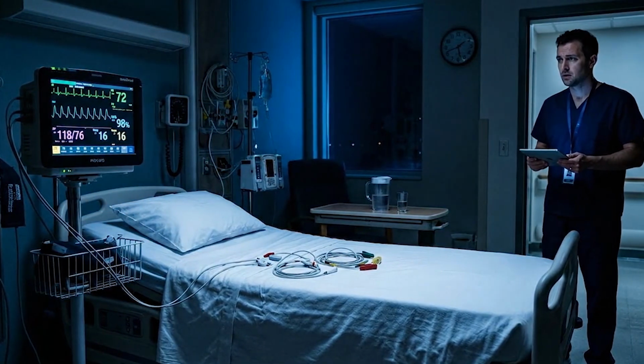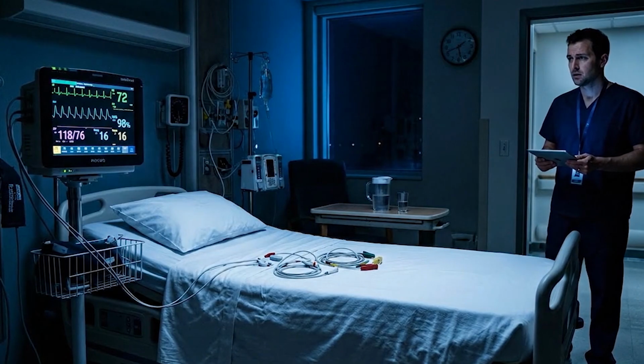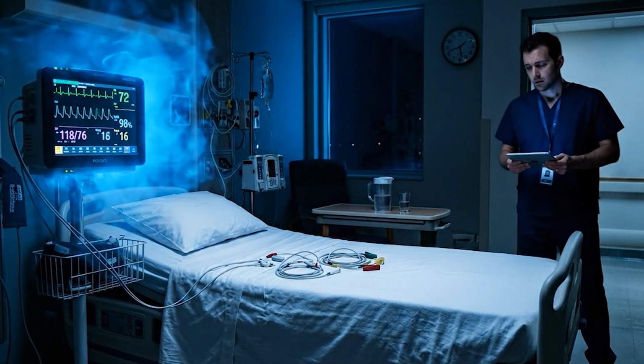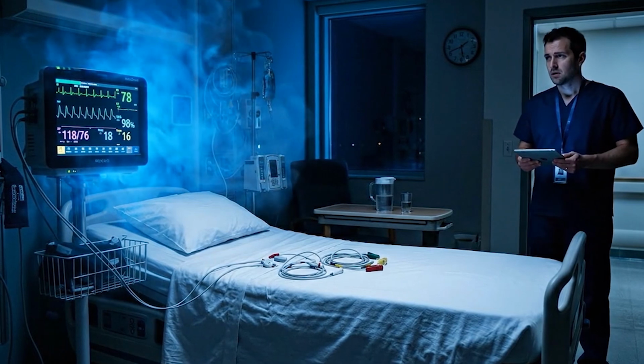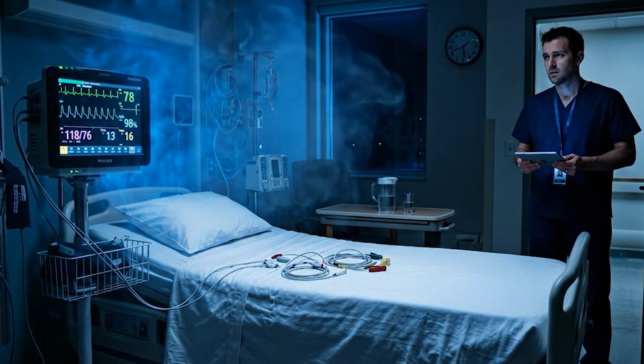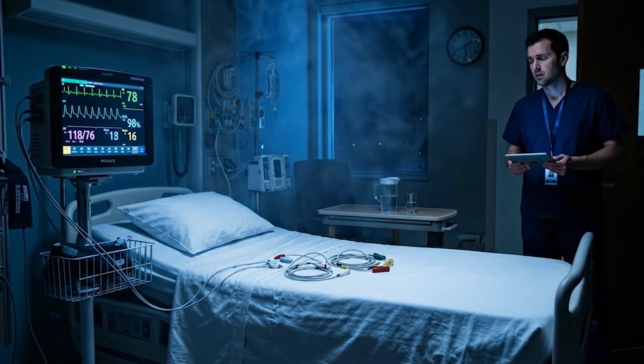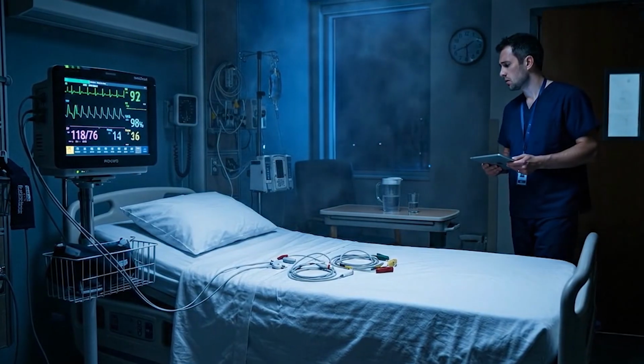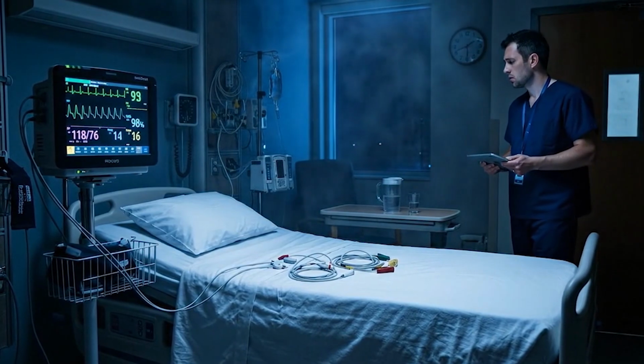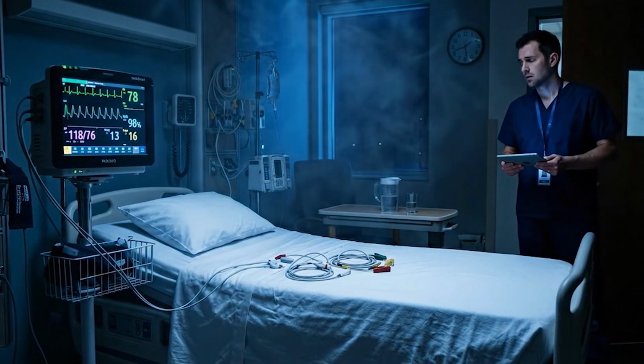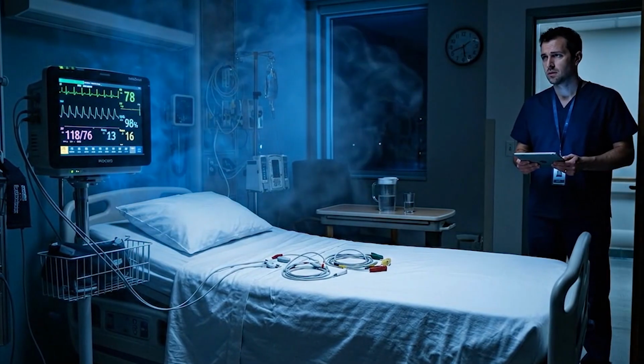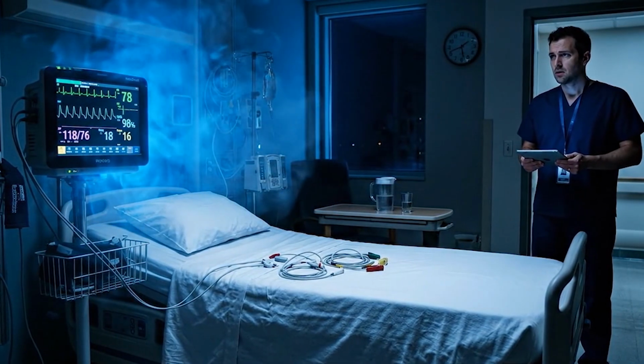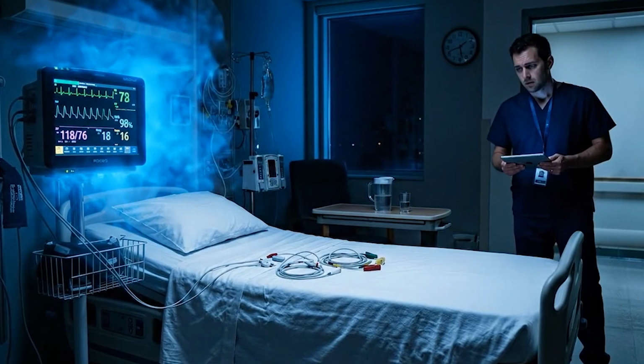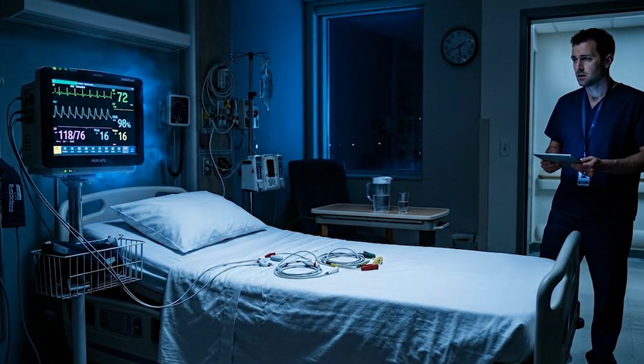The device thought it was working correctly because, as far as its own systems could determine, it was working correctly. It was receiving data on all channels, and the data was clinically valid. The fact that the data was coming from an empty bed was not something the monitor's diagnostics could detect, because the monitor doesn't know what's in the bed. It only knows what its sensors report.